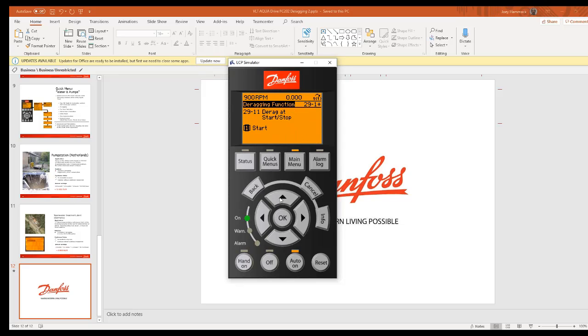function. So I'll just set it to start and set these parameters, and then just give the drive a start command, and it will DERAG. And then when I'm done, okay, it's clear, he doesn't want to keep it going, then I just turn that function back off, and it won't DERAG again until next time. Or you can leave it on and say now it's not going to DERAG. So that's one easy way.